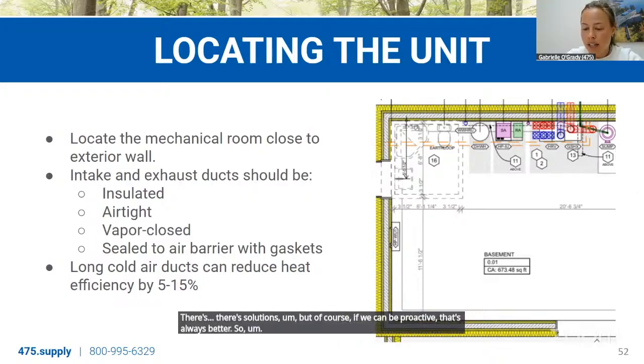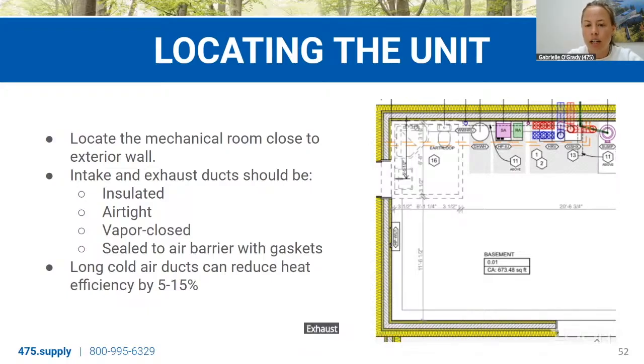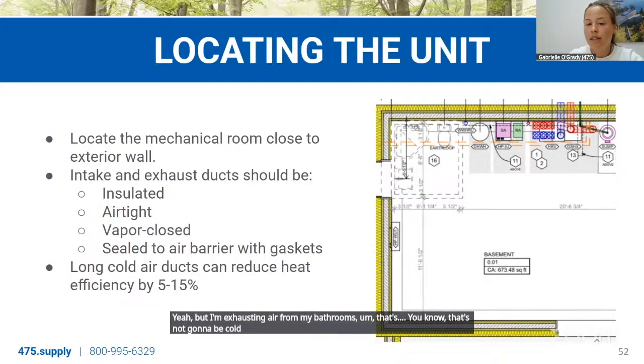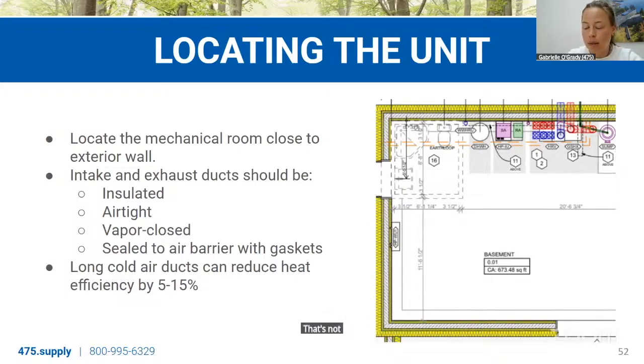So insulate that duct, and then also insulate our duct that's exhausting the air to the outside after the heat recovery core. This is sometimes not as intuitive because we know in the winter, cold outside air goes into the core. Yeah, but I'm exhausting air from my bathrooms. That's not going to be cold. When it's in the 3-inch ductwork, that's the same temperature as your home. But after the heat recovery core, the main duct that leaves your envelope, because the core is so efficient, that's also going to be pretty cold. So we do also want to insulate that and keep that as short as possible as well.